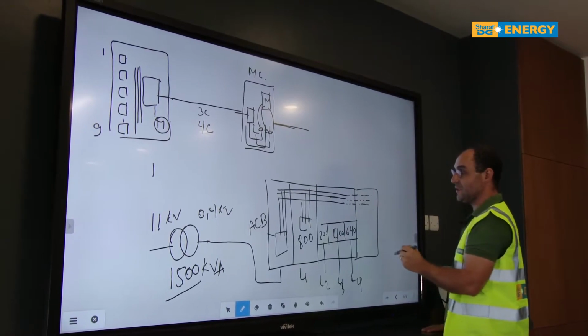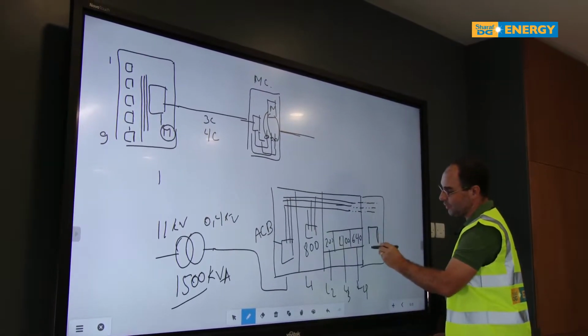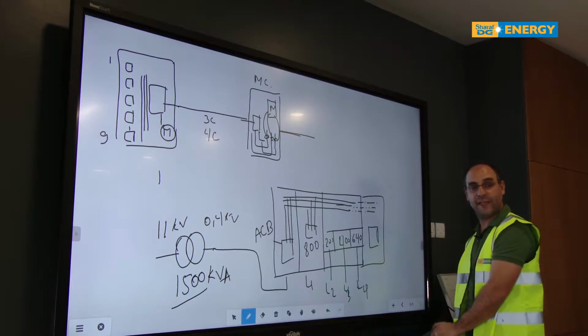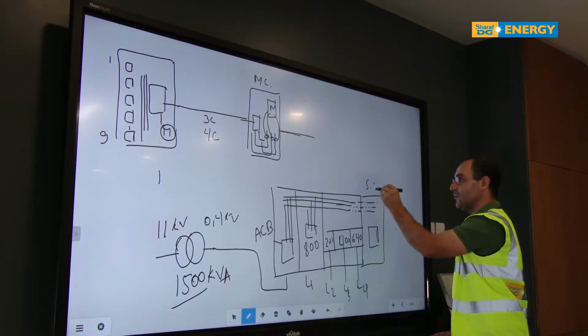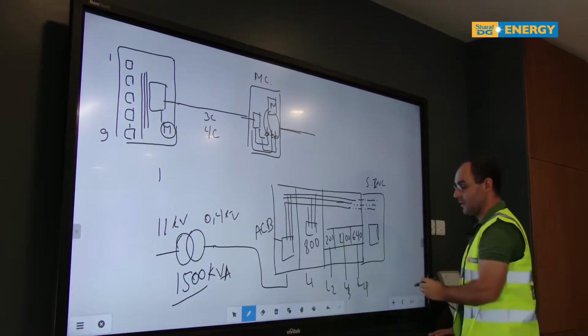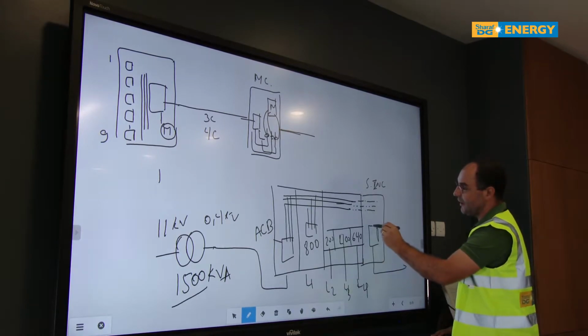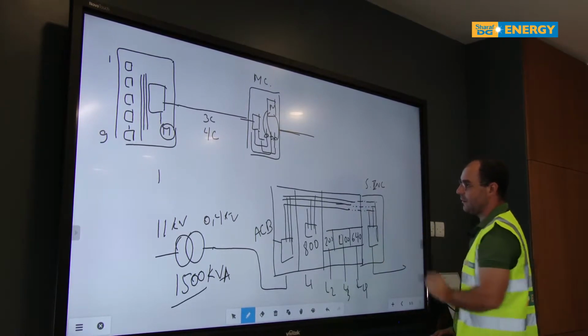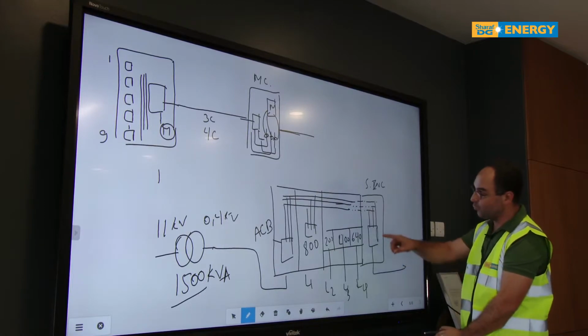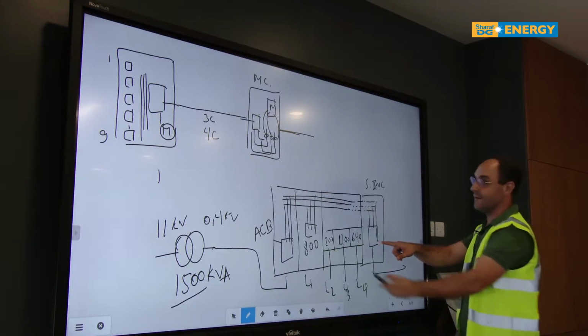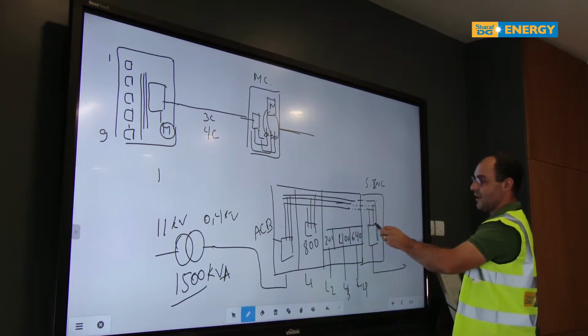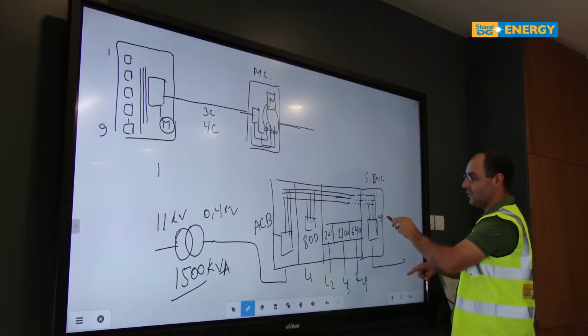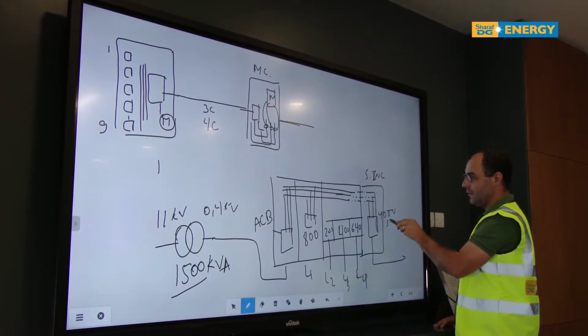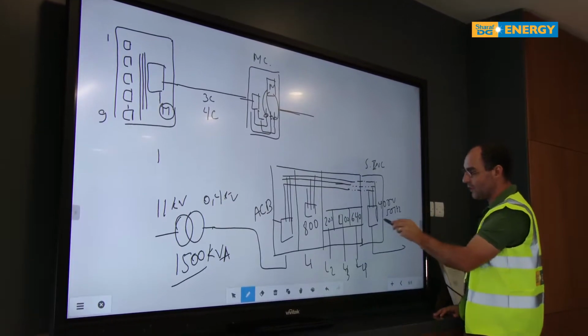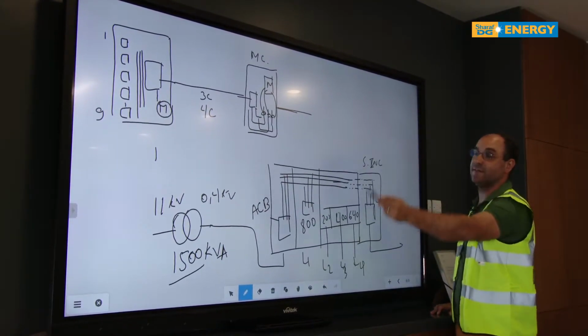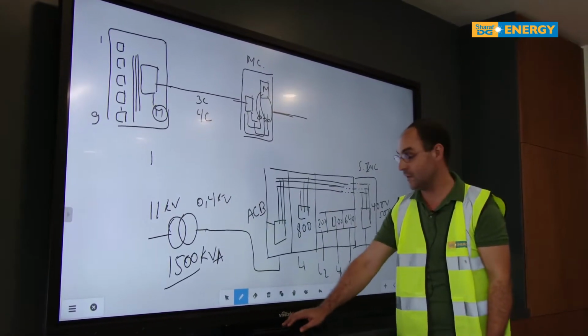We extend the bus bars and put our solar breaker, what you call solar incomer. Our cables come from here, and from here we are hooked up again. If you put this breaker on, the frequency and voltage that are here now from DEWA, 50 Hertz, will be aligned to our inverter level. Are you with me?